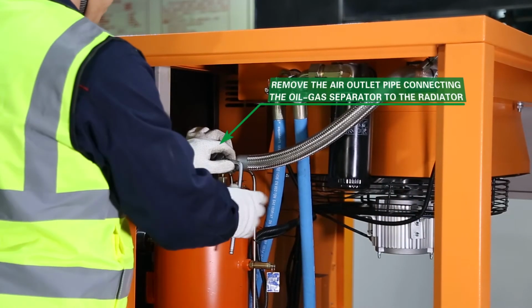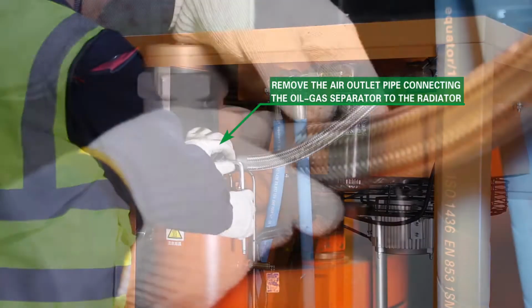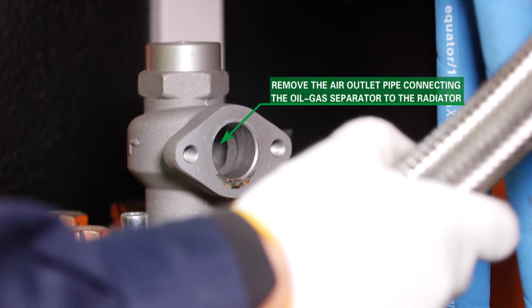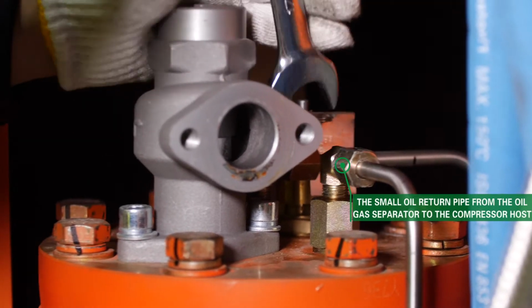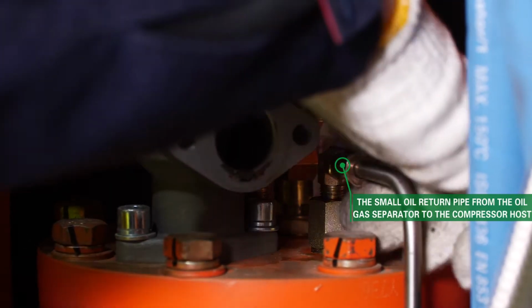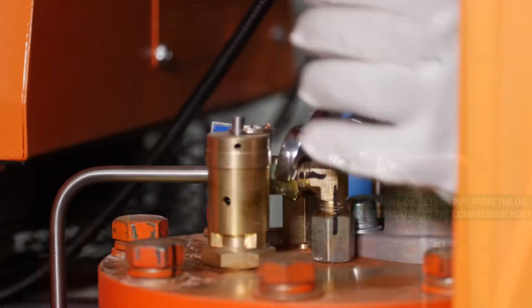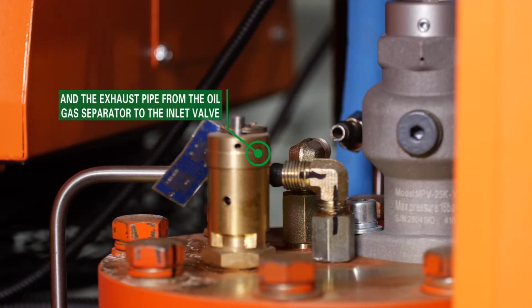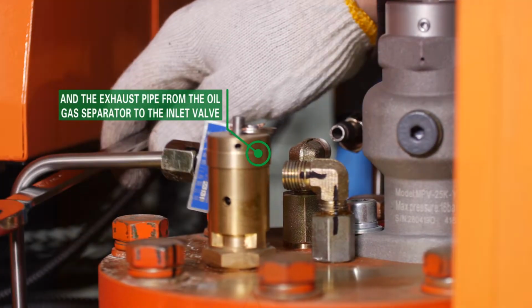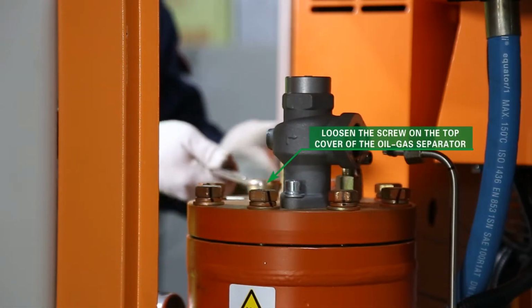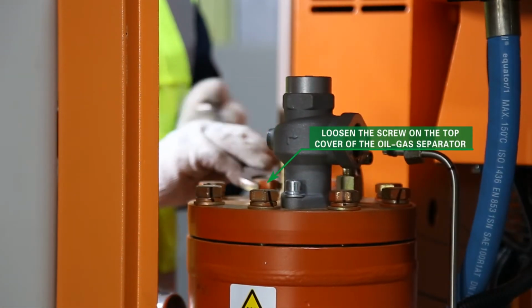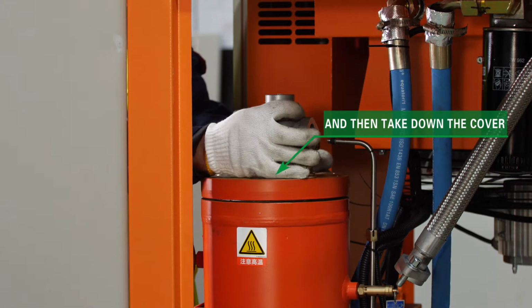Remove the air outlet pipe connecting the oil-gas separator to the radiator, the small oil return pipe from the oil-gas separator to the compressor host, and the exhaust pipe from the oil-gas separator to the inlet valve. Loosen the screw on the top cover of the oil-gas separator, and then take down the cover.